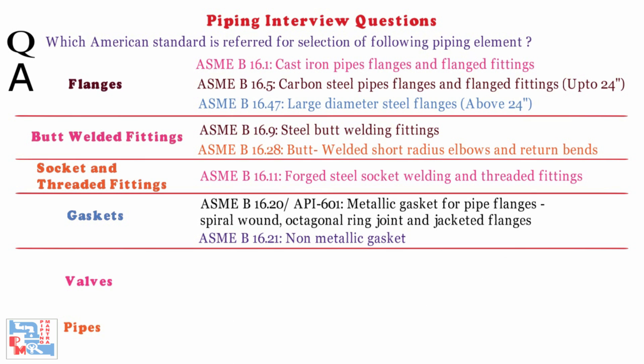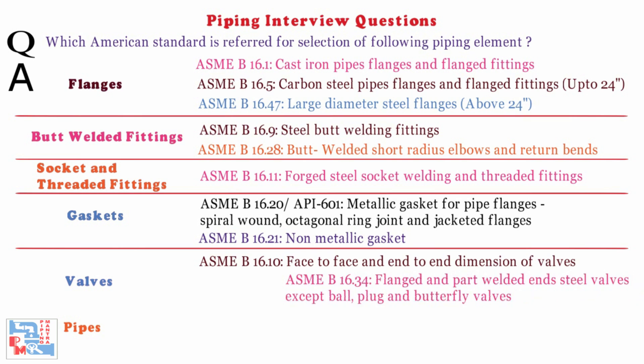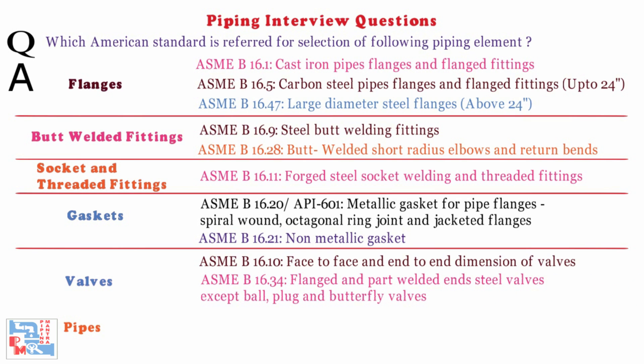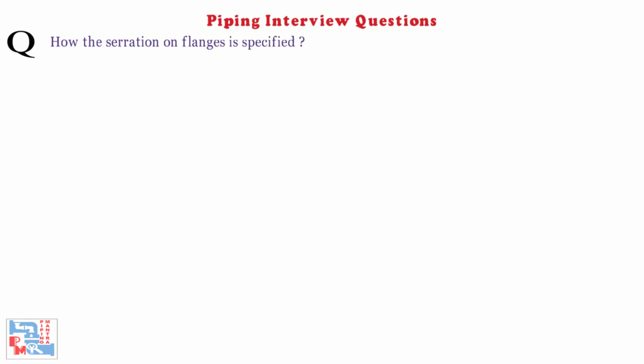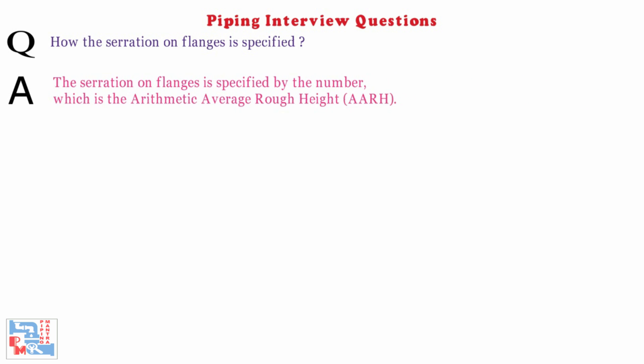ASME B16.21 is for non-metallic gaskets. For valves: ASME B16.10 is for face-to-face and end-to-end dimensions of valves. ASME B16.34 is for flanged and butt welded end steel valves covering pressure and temperature ratings, except ball, plug, and butterfly valves. For pipes: ASME B36.10 is for welded and seamless wrought steel pipes, and ASME B36.19 is for stainless steel pipes.